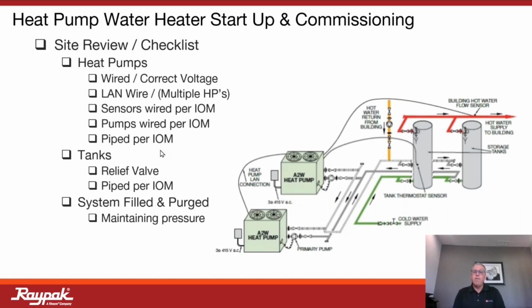This is actually a fairly straightforward, somewhat small presentation, short in length, I mean to say. And we're going to go through all this in terms of a site review, showing up. Is the wiring correct, which is a big aspect of it? Our local area network wire, our LAN wiring, that basically, if it were a boiler or a water heater, we would say it's cascaded. But in the heat pump world, they use the terminology of a LAN. Sensors, we're going to look at proper landing of the sensors, the proper wiring of the circulators. Is it piped per the IOM? Tanks, are the tanks piped per the relief valve? So all these things prior to a startup and commissioning, this is important.